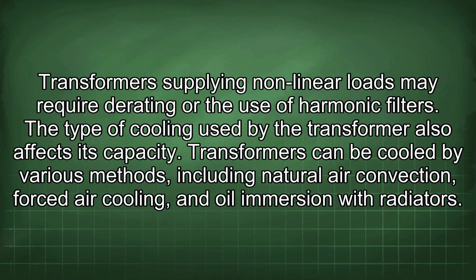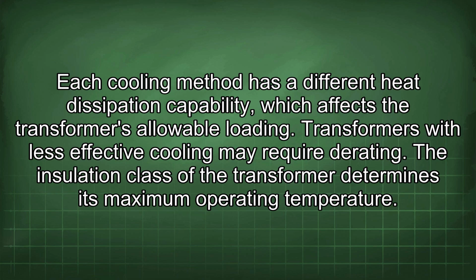The type of cooling used by the transformer also affects its capacity. Transformers can be cooled by various methods, including natural air convection, forced air cooling, and oil immersion with radiators. Each cooling method has a different heat dissipation capability, which affects the transformer's allowable loading. Transformers with less effective cooling may require derating.